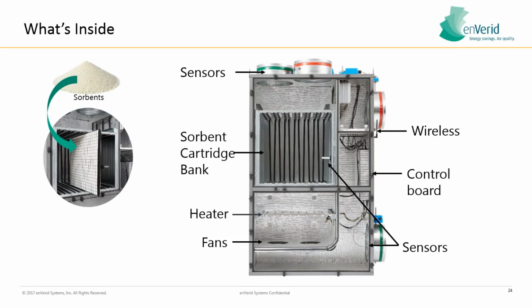So you can apply your kWh rate or your cost of heating or cooling energy per CFM, and kind of back into those numbers. Typically, we hear numbers somewhere between $4 and $8 per CFM cost of heating and cooling air. So if you're reducing 2,000 to 3,000 CFM at $4 to $8 per year, you're looking at $8,000 to $12,000 worth of savings potentially in many regions. It varies region by region. We also have a little heater on this unit. Basically, these cartridges have the ability to regenerate themselves for air cleaning capacity.